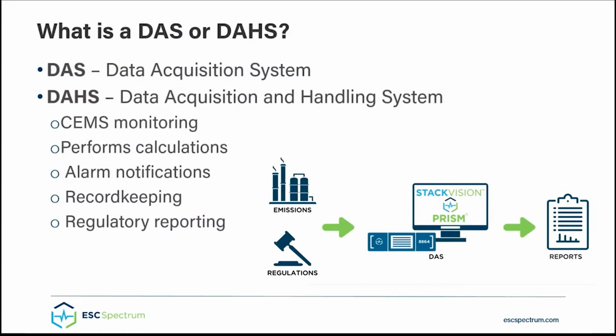Let's start with the acronyms. Whether you refer to a DAS as a data acquisition system or data acquisition and handling system, we're talking about the same thing. The primary functions of a DAS are to monitor the air emissions data from a plant's continuous emissions monitoring system, or CEMS, perform the calculations necessary for regulatory reporting, manage alarms that alert environmental and operation staff about potential emissions exceedances or operational issues, maintain a secure database of historical records, and automate regulatory reporting.